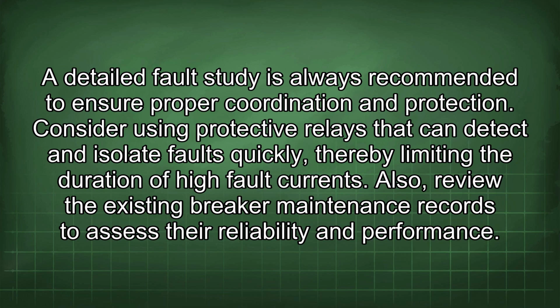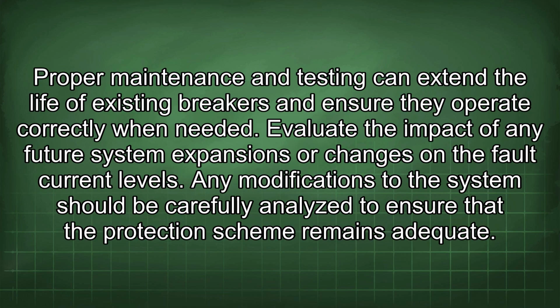Consider using protective relays that can detect and isolate faults quickly, thereby limiting the duration of high fault currents. Also, review the existing breaker maintenance records to assess their reliability and performance. Proper maintenance and testing can extend the life of existing breakers and ensure they operate correctly when needed.